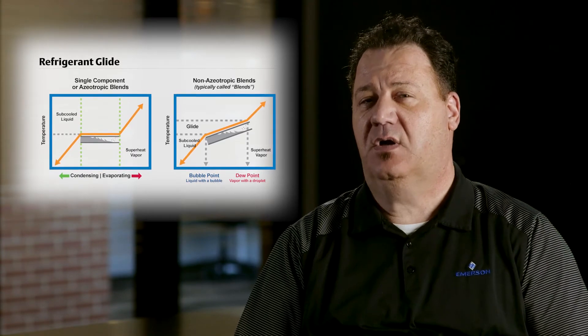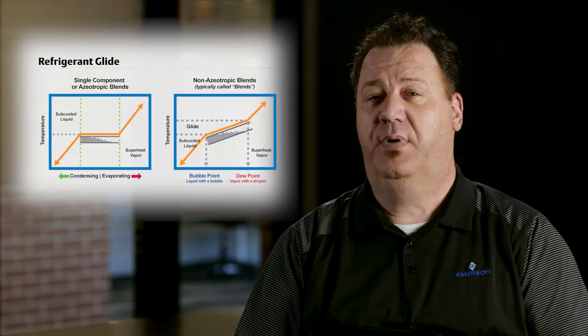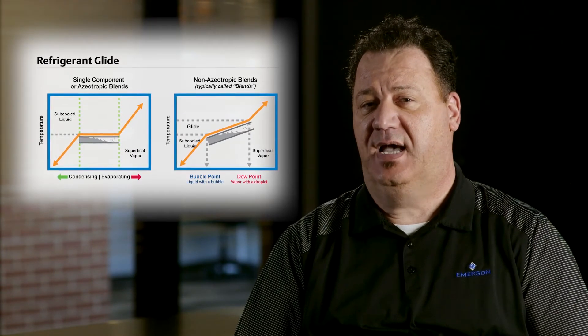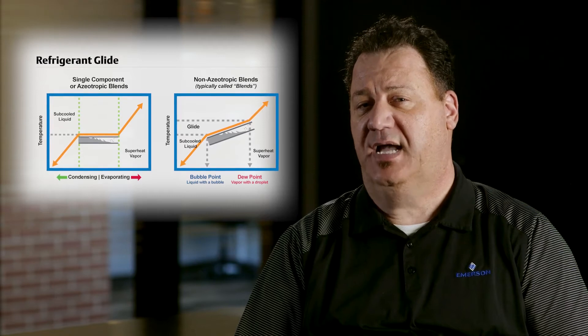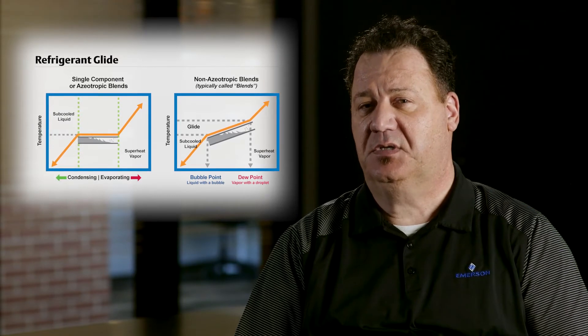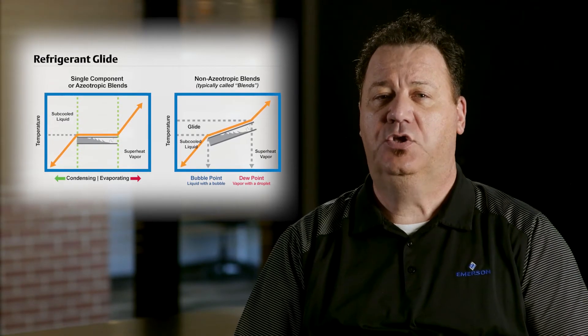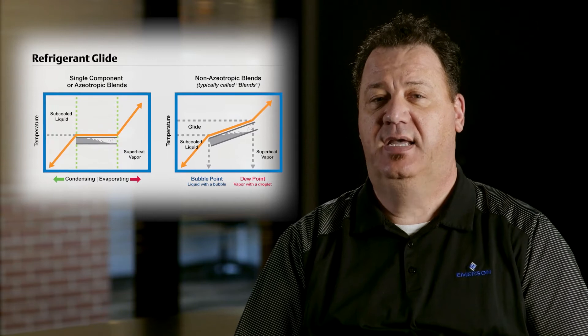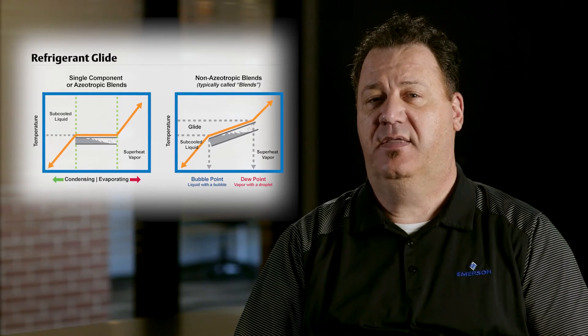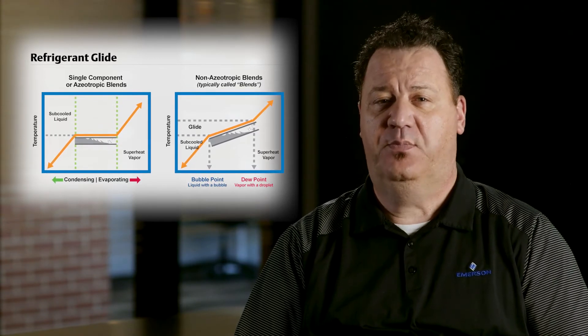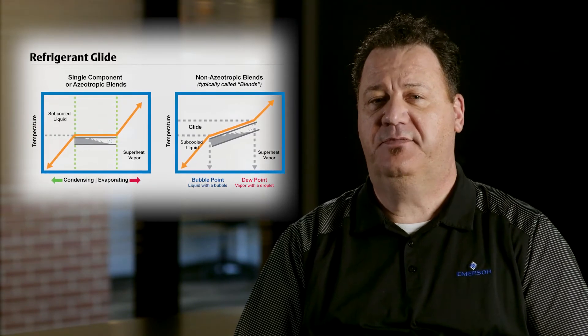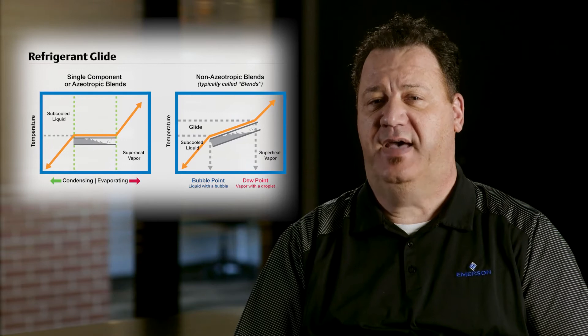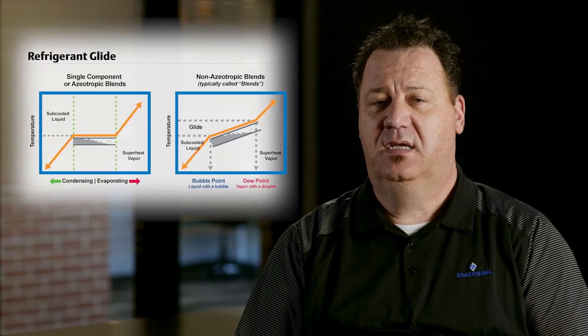We start out with our bubble point, which is our liquid side entering our saturation temperature, and we end with our dew point, which is our saturation entering that vapor point. The difference in those two is in fact our Glide.